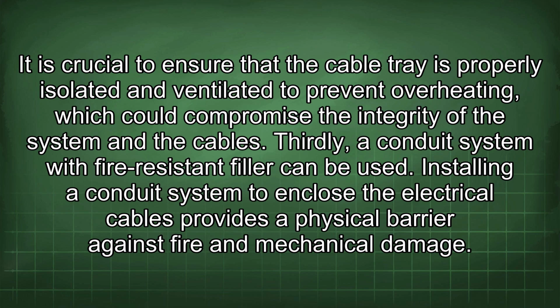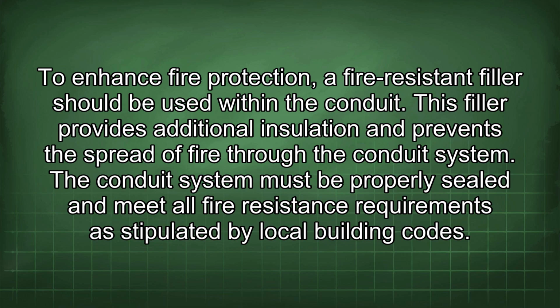Thirdly, a conduit system with fire-resistant filler can be used. Installing a conduit system to enclose the electrical cables provides a physical barrier against fire and mechanical damage. To enhance fire protection, a fire-resistant filler should be used within the conduit. This filler provides additional insulation and prevents the spread of fire through the conduit system. The conduit system must be properly sealed and meet all fire resistance requirements as stipulated by local building codes.